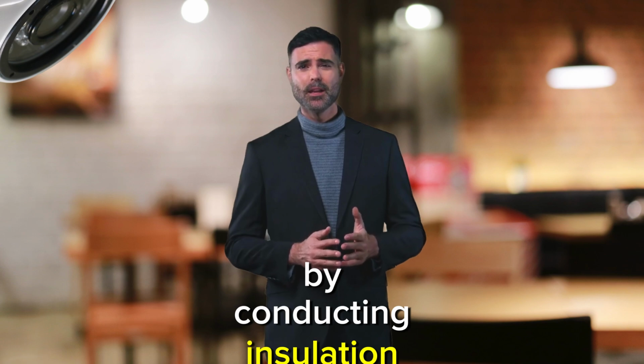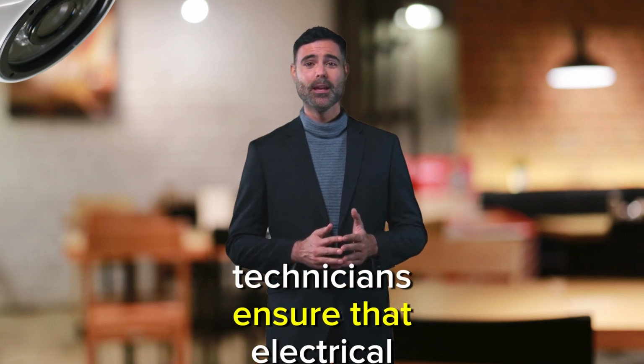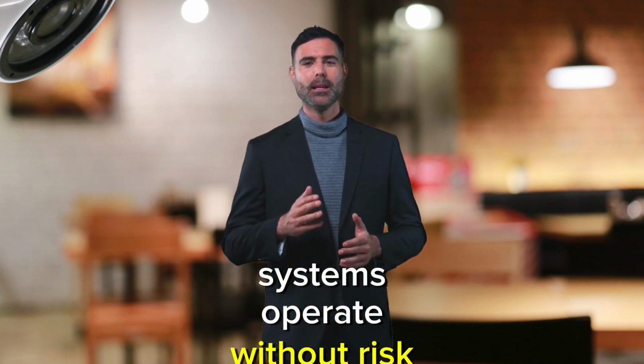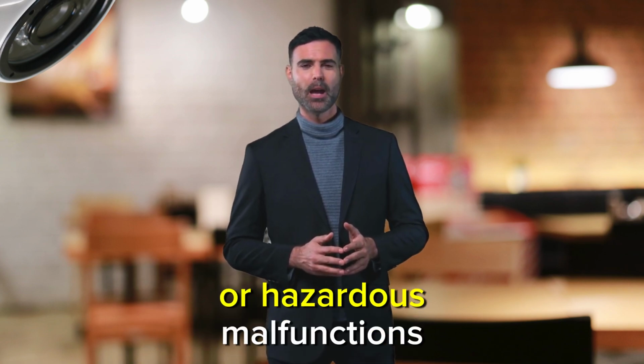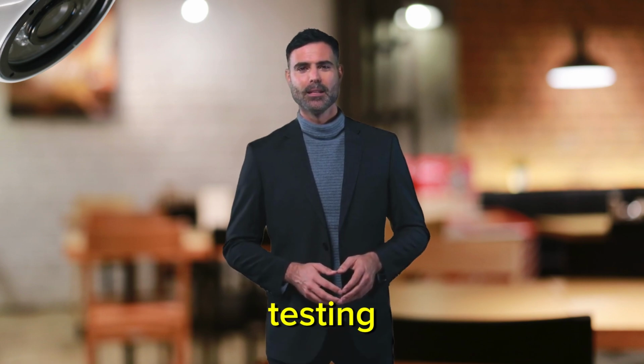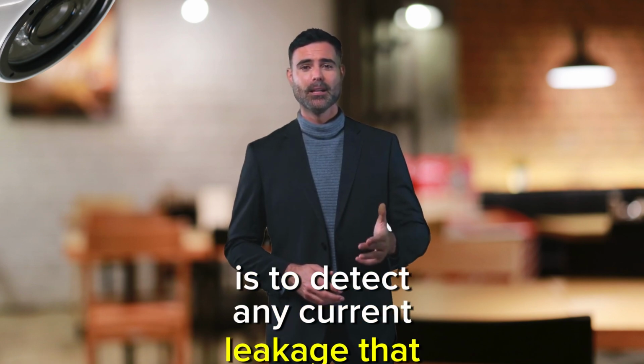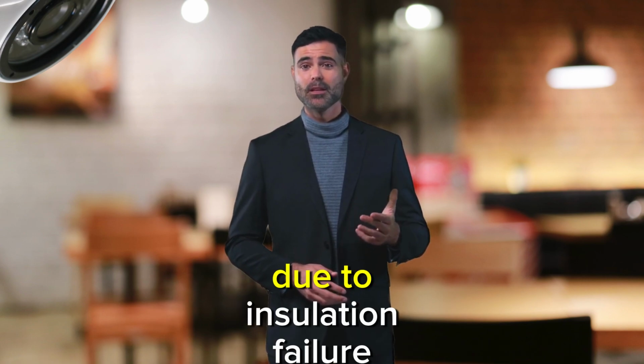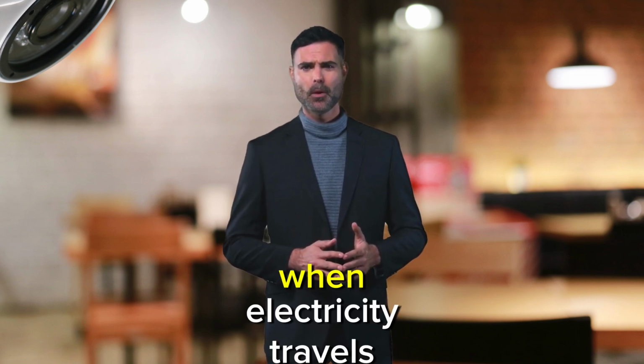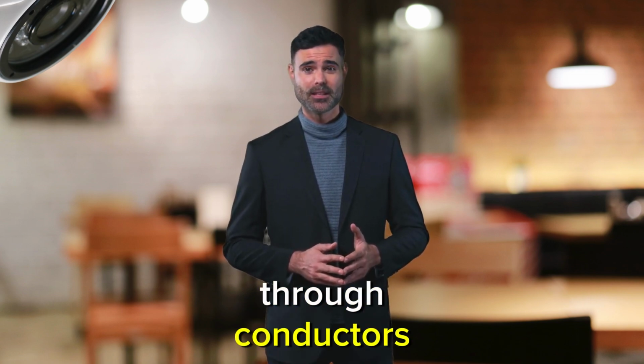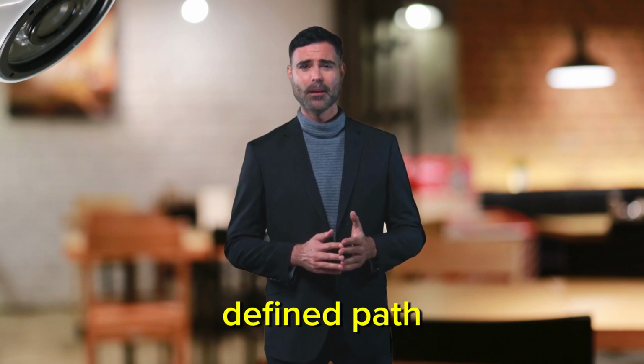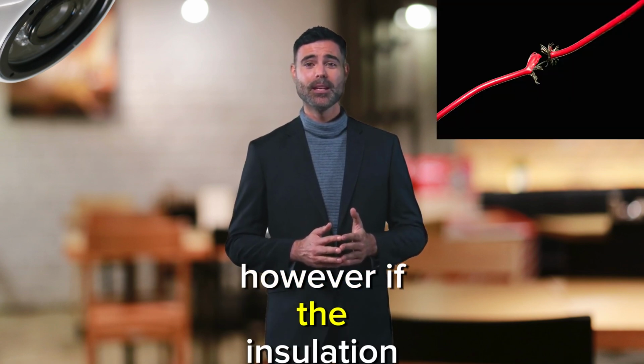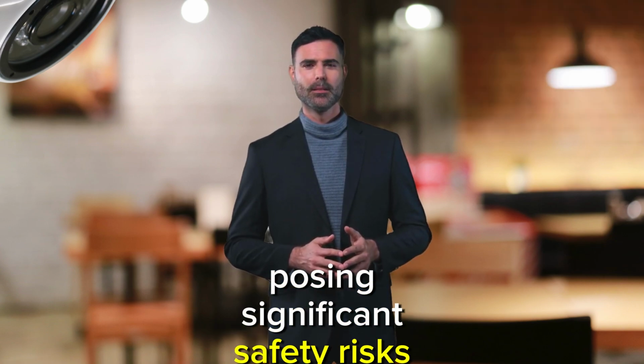By conducting insulation tests, technicians ensure that electrical systems operate without risk of unnecessary energy loss or hazardous malfunctions. The primary goal of insulation testing is to detect any current leakage that may occur due to insulation failure. When electricity travels through conductors, it ideally remains within the defined path. However, if the insulation becomes compromised, some of this current can escape, posing significant safety risks.